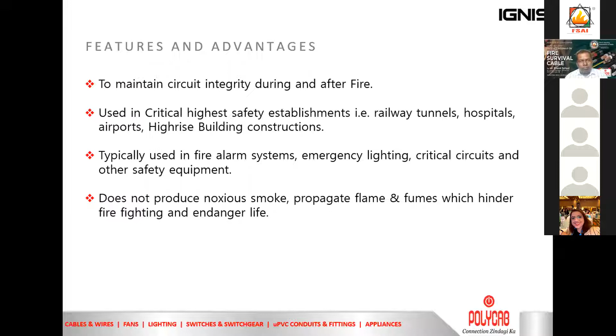So fire resistance, long-term circuit integrity, low smoke and very low toxic gas emissions. Flame retardancy, zero halogen, easy and low cost installation—nothing special is required to install these cables, easy to implement in circuits. If your existing circuit needs enhancement or rectification, you can put the FS cable, no issue. Features and advantages include circuit integrity used in critical highest safety establishments and railway tunnels, typically used in fire alarm systems, emergency lighting, critical circuits, and other safety equipment. It doesn't produce noxious smoke, propagate flames, or produce fumes which hinder firefighting and endanger life.